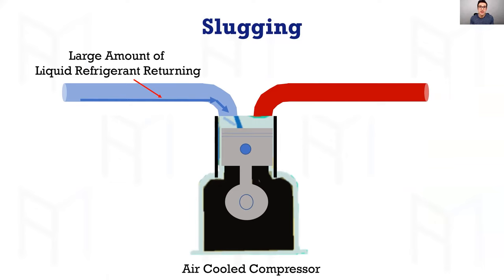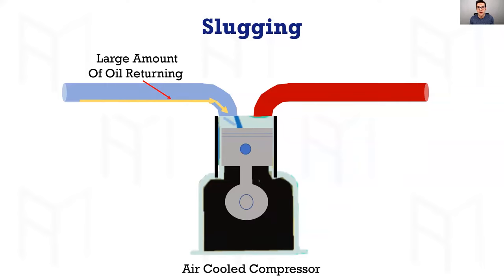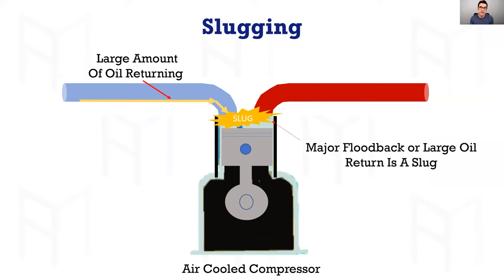It cannot absorb the heat to boil off, so you have no superheat and liquid starts making its way back — or it could be oil. A large amount of oil returning could be due to insufficient defrost, too much oil in the system, or improper slope. All of a sudden you have a slug, and you'll see broken suction or discharge valves inside and bent backers on the valve plate. Take the head off to see what happened and why the compressor isn't pumping. Major flood backs or large amounts of oil returning to the air-cooled compressor cause the slug.